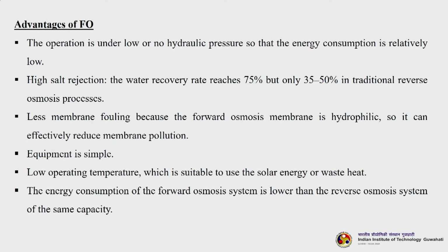High salt rejection. Actually, the water recovery rate reaches about 75%, but only 35 to 50% in traditional reverse osmosis processes. Less membrane fouling, because the forward osmosis membrane is hydrophilic, so it can effectively reduce membrane pollution. Equipment is relatively simpler. Low operating temperature also makes it suitable to use solar energy or waste heat. So, the energy consumption of the forward osmosis system is lower than the reverse osmosis system of the same capacity.